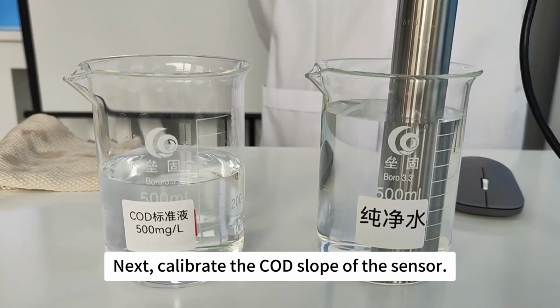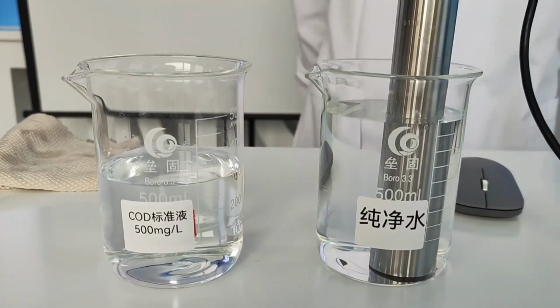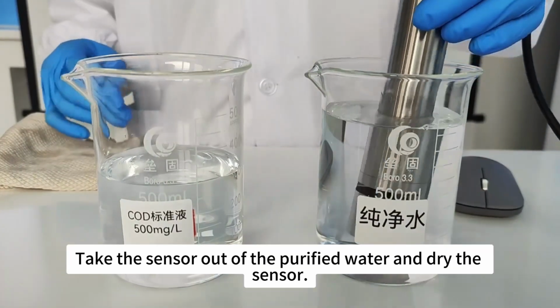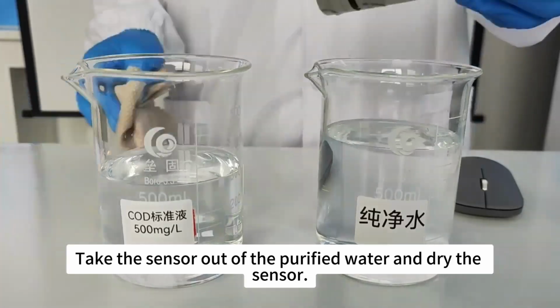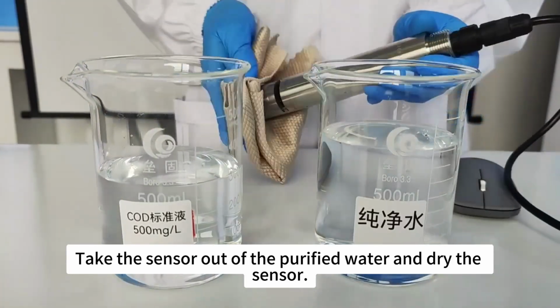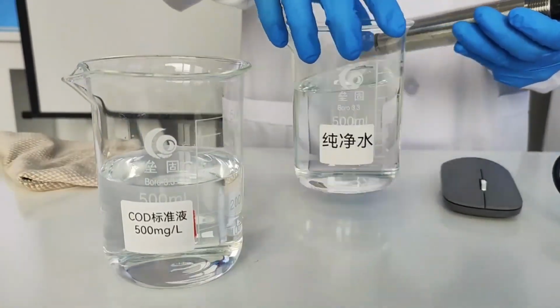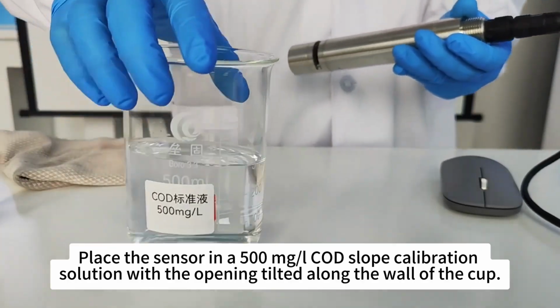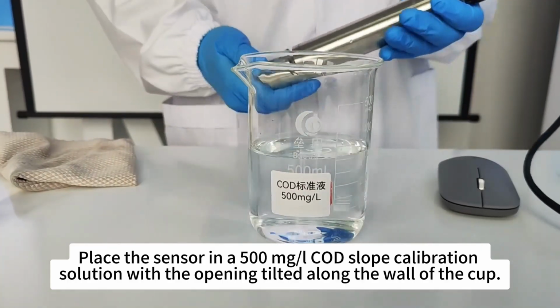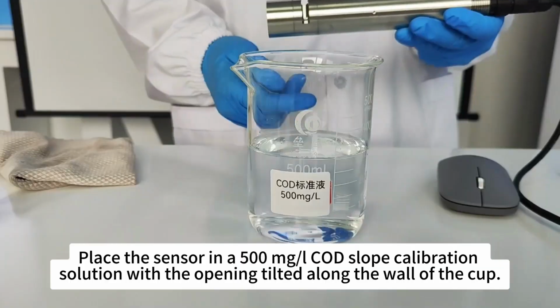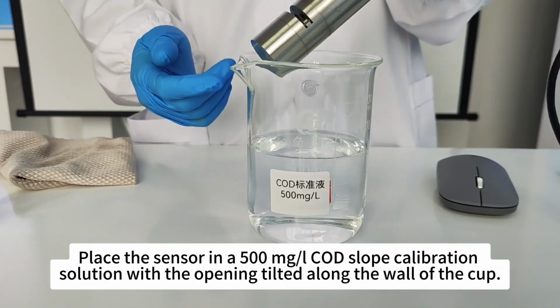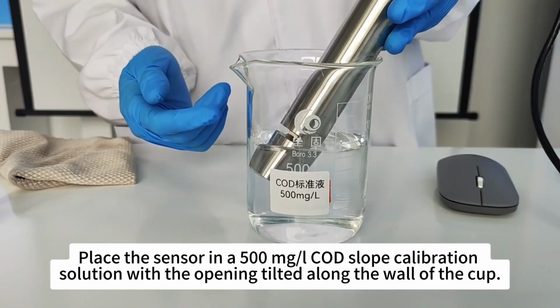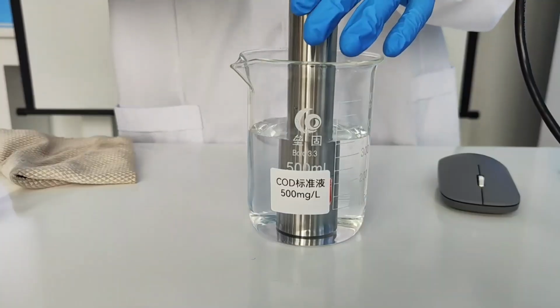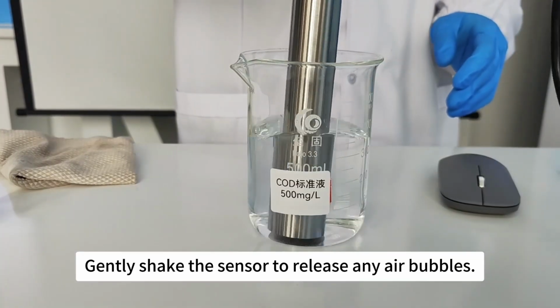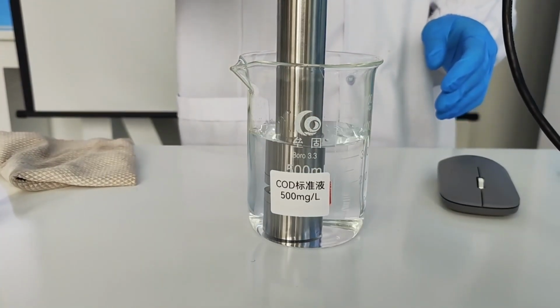Next, perform the COD slope calibration of the sensor by taking the sensor out of pure water and drying the sensor. Place the sensor in a 500 mg per liter COD slope calibration solution with the opening tilted along the wall of the cup. Gently shake the sensor to release any air bubbles.